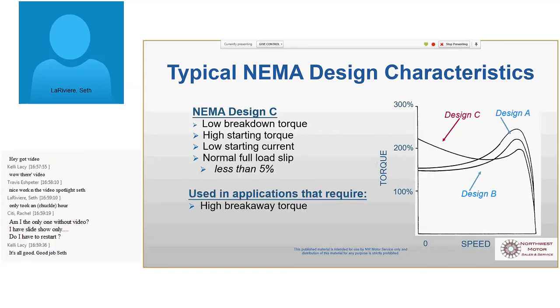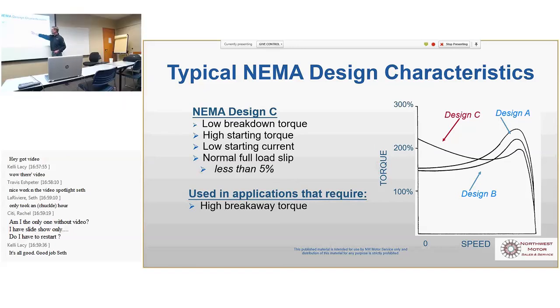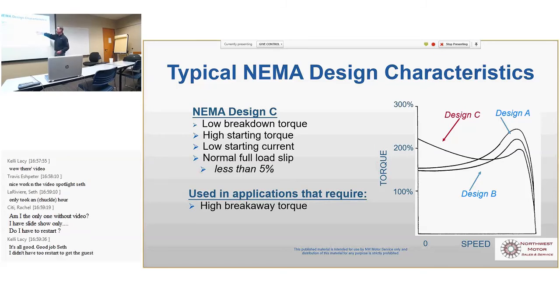Design C, you'll see those a lot on hard to start compressors. You usually see them up around 200 horse and above. I don't think I've seen a lot lower than that. You might, but generally they're in the larger horsepowers. They have kind of an unusual starting torque curve. They give you additional starting torque at the beginning, but they don't give you as much breakdown torque at the end. So these are really used to start hard to start applications like chippers, anything that's got a lot of inertia that you're trying to start. You see a lot of NEMA Cs.